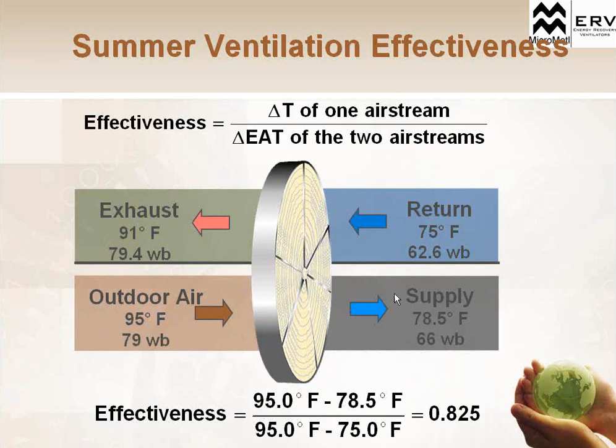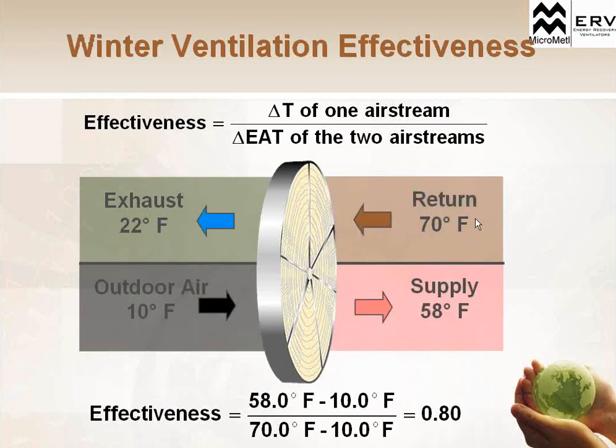So in this instance, we had 95-degree outdoor air to 78-degree supply air. And then we had 95-degree outdoor air coming in, and our return was 75 degrees. So how much of that 75 degrees was I able to recoup with that energy recovery wheel? In this instance, this specific wheel is 82.5% effective, a percent effectiveness. That's typically what you'll see of a lot of wheels, 60 to 80% effectiveness. These are really great heat transfer devices. We'll talk about the materials in each one of them.